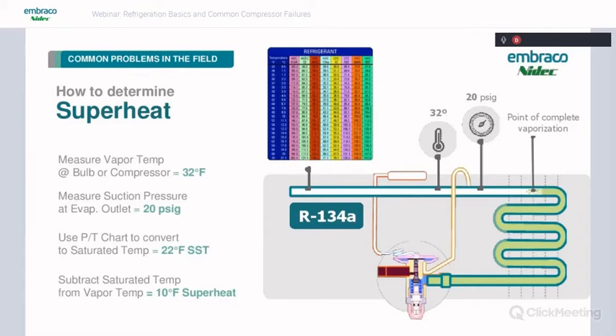So the lower your superheat, the more excess refrigerant is making its way through the evaporator. If you're measuring superheat at the compressor and you get 5 degrees of superheat or even 0 degrees, then you're getting liquid refrigerant returned to that compressor. Could be several different reasons. You could have a blower motor that's not working well. You could have a dirty air filter, anything that's causing low airflow across the evaporator.